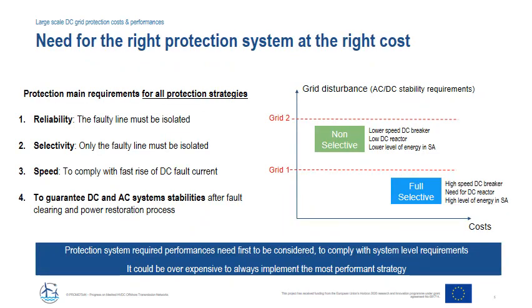All protection systems must comply with various requirements. Among them, reliability and selectivity ensure that the faulty line will be isolated. Speed is required to deal with the fast rise of the DC fault current and can lead to the use of devices which limit current rise, such as DC reactors. DC grid fault clearing strategies could impact the frequency and transient stability of the AC transmission system surrounding the DC network due to the temporary disruption of DC power flow that can reach values of several gigawatts for 100 to 200 milliseconds. The impact on AC system stability is strongly dependent on the power fraction prior to fault inception and on the value of the system inertia.